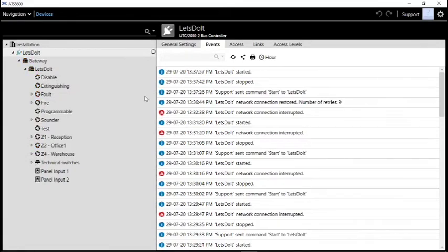So it's definitely not a configuration fault on the Ziton panel or the Kielson or whatever it is. And it's not a configuration in the ATS software. This is all just Windows backend issues. We haven't changed the network, and the USB has been plugged out. So there's definitely nothing prohibiting the fire panel from connecting.